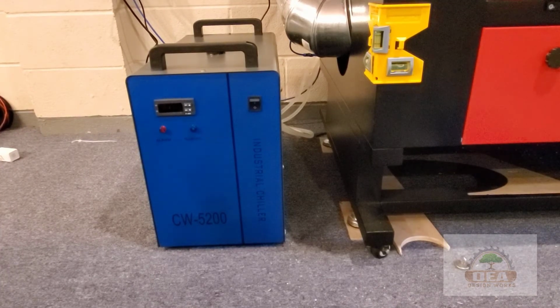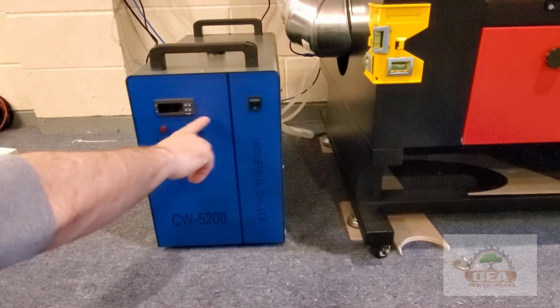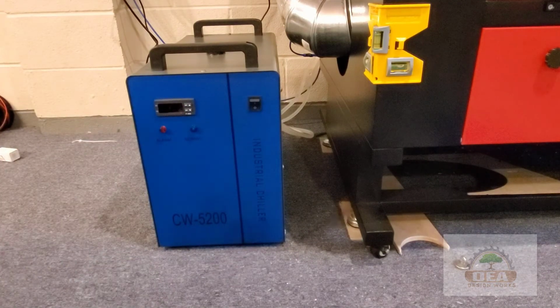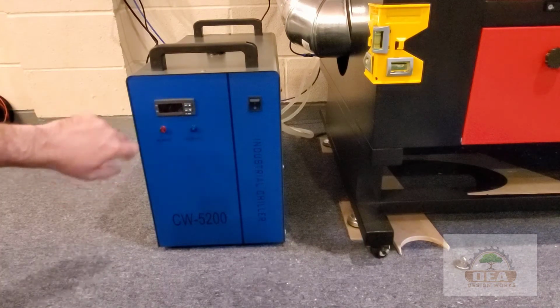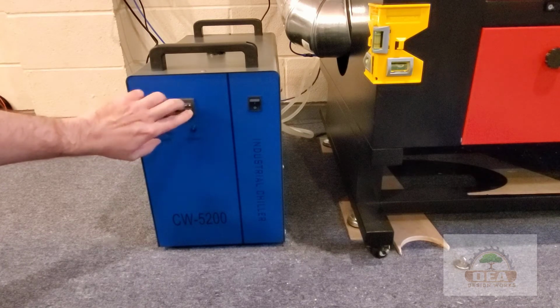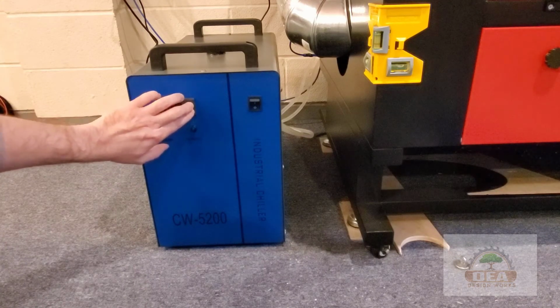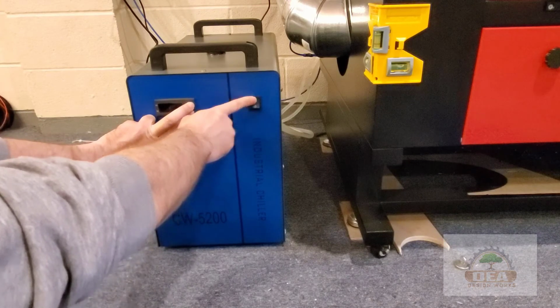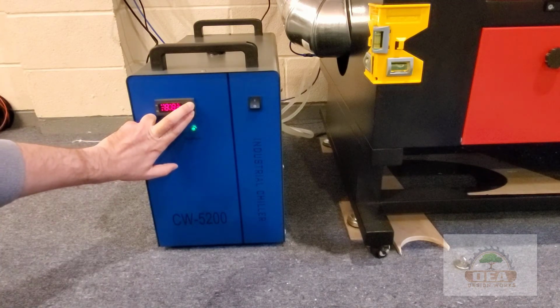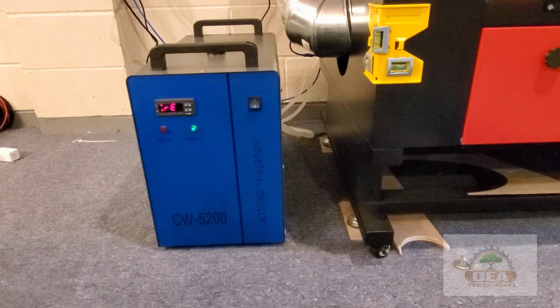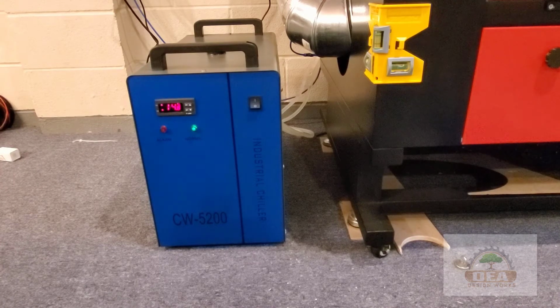Okay, so to reset the chiller, we need to hold the up arrow and the down arrow and then turn on the power switch. And what we'll see is an RE on the screen here. So I'm going to go ahead and push both of those arrows. Make sure you get the right side of the arrow. Try to get my fingers out of the way. I'll turn it on. We get some beeping. Continue to hold. And now we see the RE. So the chiller is now reset. It's going to go back and it's going to show a temperature. And now we're ready to start programming.